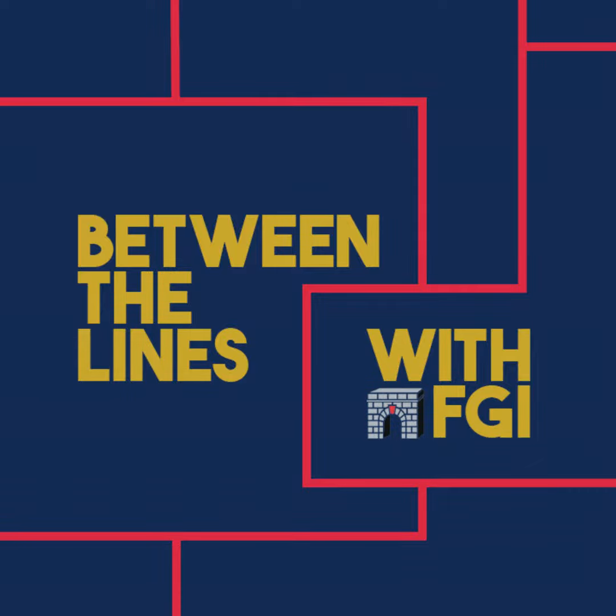All right, I think that quench that you talked about probably caused some conditions inside of the room that were a little extreme. There's a new section of the guidelines that talks about building and occupant protection, and it says we have to have emergency exhaust and passive pressure relief, and it shall be provided in that room in accordance with manufacturer specifications. What does that look like? Okay. So working from the assumption that a quench pipe may fail, right? Our chimney may not effectively convey all of the helium gas that we want to the outside.